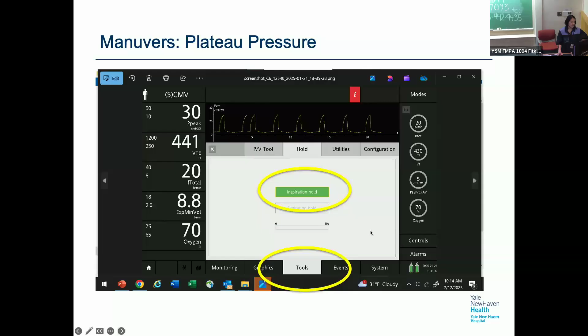Once you do that, this screen will appear. It will be a frozen waveform. And what you see here on the pressure time curve is a flat plateau. You will use the knob on the ventilator to scroll the cursor to a 0 flow setting, so where flow is 0. And flow is being reported over here.